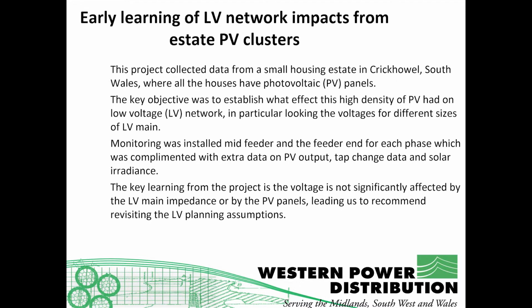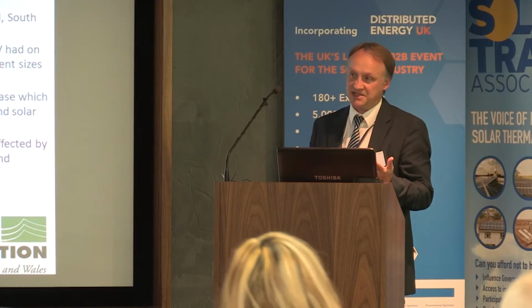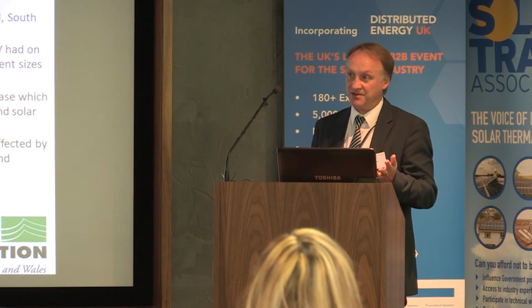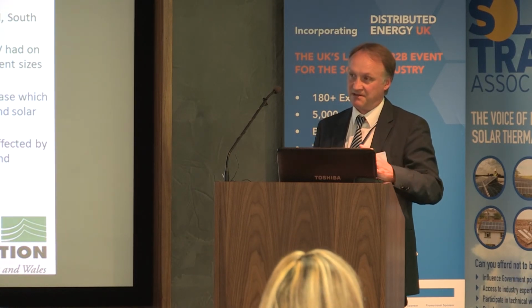Okay, moving on to the early learning project, and this was a lot smaller project. This is a Tier 1 project, and it collected data from a small housing estate in Crickhowell, South Wales, where all the houses are new and have all been built with photovoltaic panels. The key objective was to establish what effect high density of PV would have on the low voltage network, in particular looking at the voltages for different sizes of LV mains. They ran three separate mains cables around the estate, a 95 Wavecon, a 185 Wavecon and a 300, and we could switch between the three and see the effects.